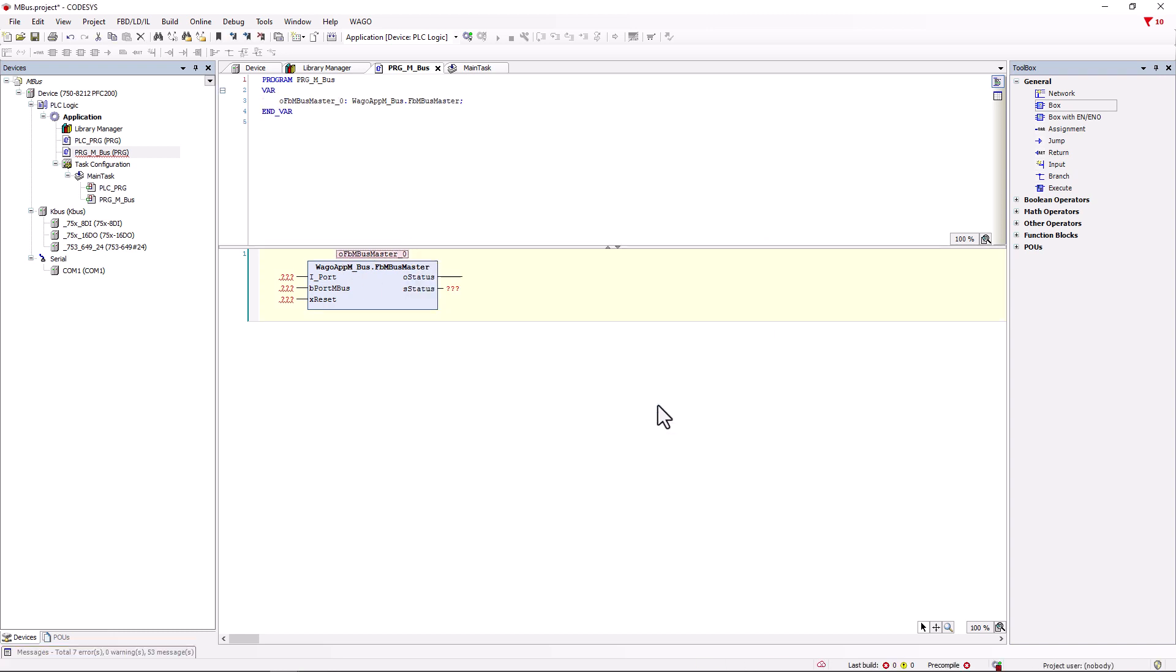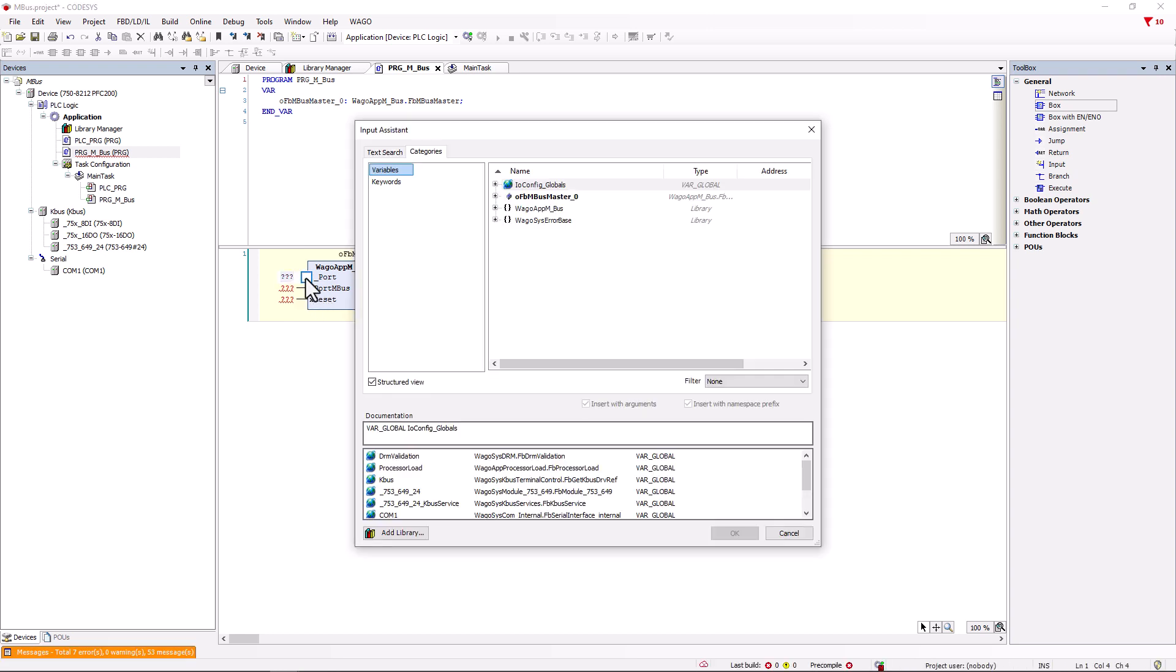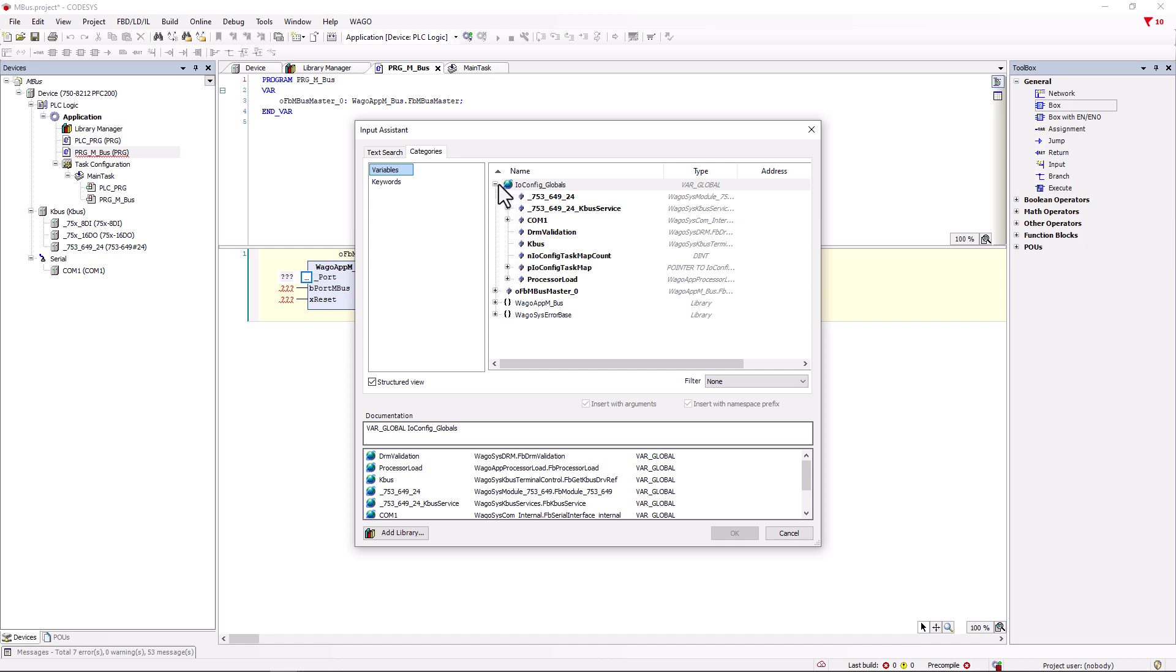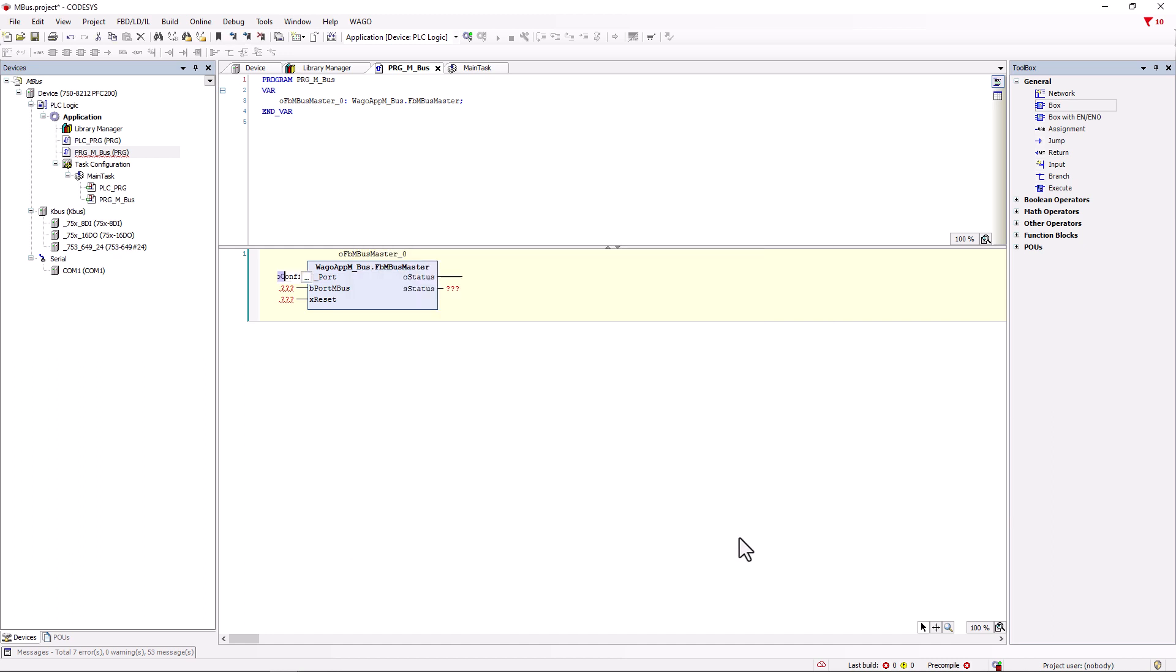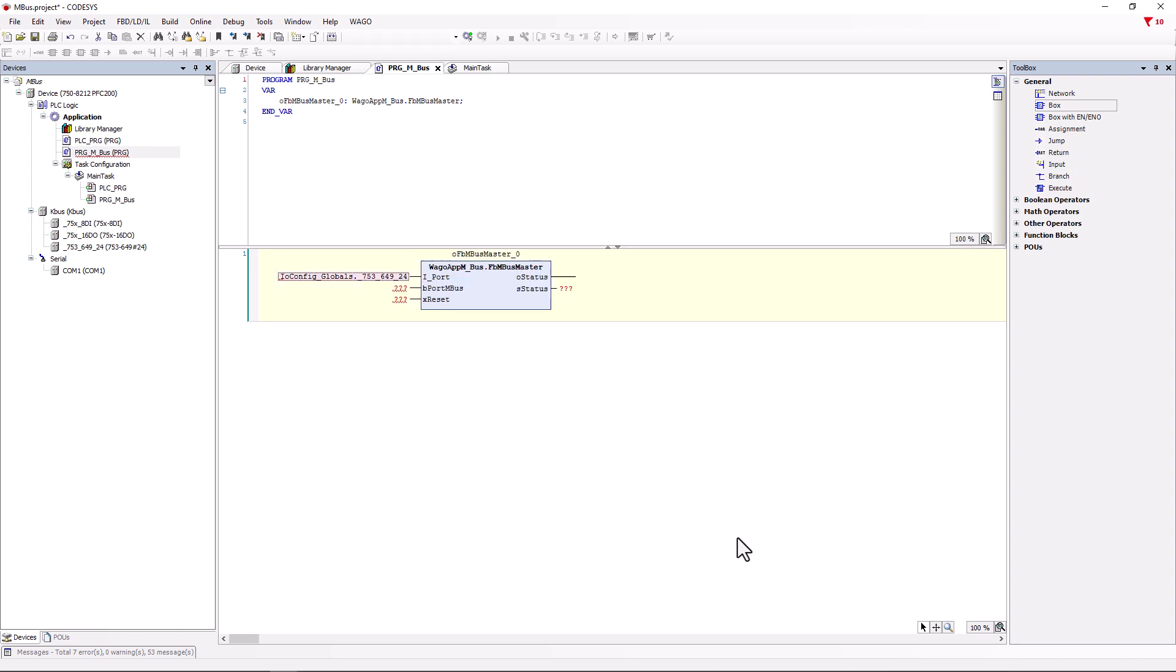The inputs and outputs of the master must now be assigned. Double clicking on the iPort opens the input wizard and we search for the MBUS module 753-649 in the IO config globals area and confirm with Enter. This connects the master module to the hardware MBUS module. The iPort is our communication to the MBUS. The master module now makes all values that pass via the MBUS available for use in the application on the B port.